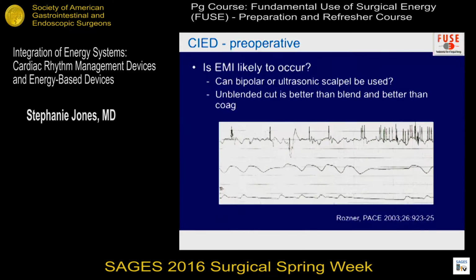So how likely is EMI to occur? The best thing is if you guys can use a bipolar or an ultrasonic, I really don't have to worry about it. But that's not often the case. And if you do have to use a monopolar device, going back to, again, what everybody else has said, unblended cut is better than blend, which is better than coag.